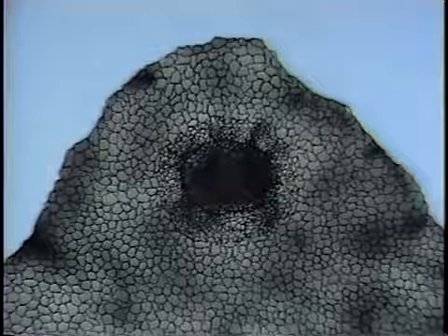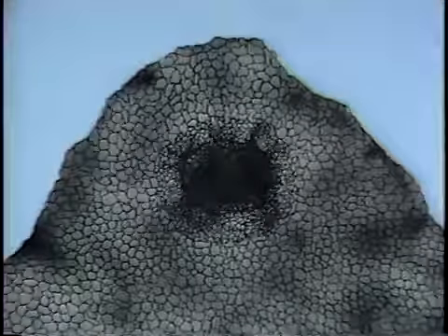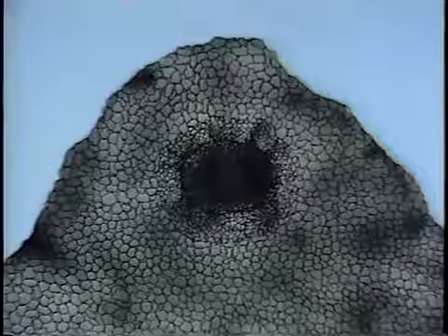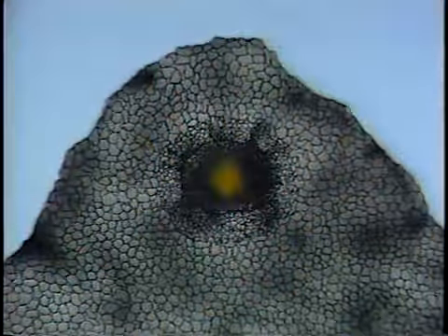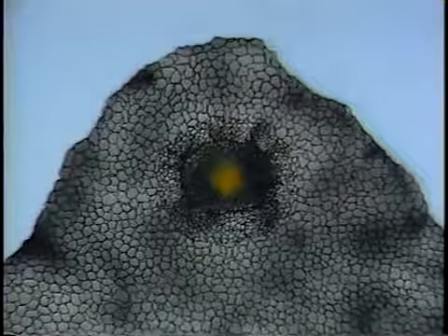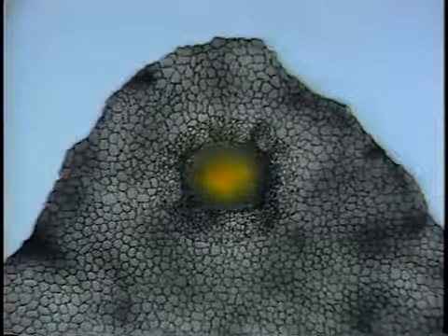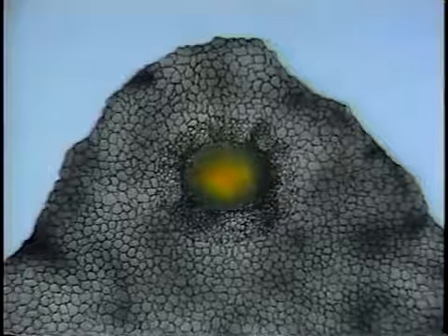We'll use this simplified drawing of a coal pile to review how spontaneous combustion occurs. Coal in the coal yard is subjected to the heat of the sun and the heat produced by decaying organic matter in the coal. In some cases, the heat is sufficient to start combustion in a small section of the coal pile. Air pockets in the pile, as well as the air in the surrounding atmosphere, keep the combustion process going. Coal pile fires are generally slow, smoldering fires that don't produce much in the way of flames. As a rule, coal yard fires do not endanger plant operation.